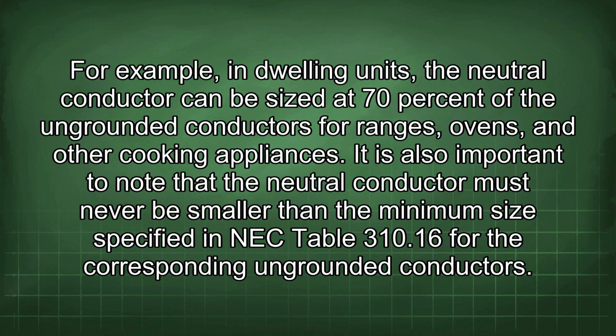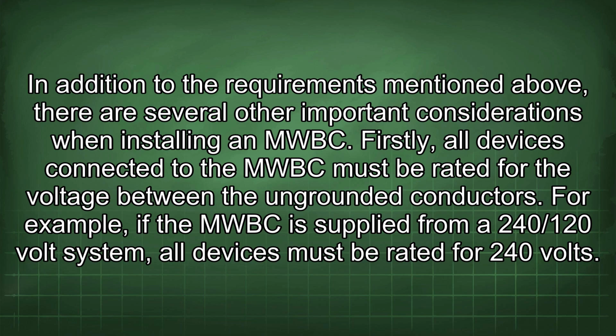For example, in dwelling units, the neutral conductor can be sized at 70% of the ungrounded conductors for ranges, ovens, and other cooking appliances. It is also important to note that the neutral conductor must never be smaller than the minimum size specified in NEC Table 310.16 for the corresponding ungrounded conductors. In addition to the requirements mentioned above, there are several other important considerations when installing an MWBC.